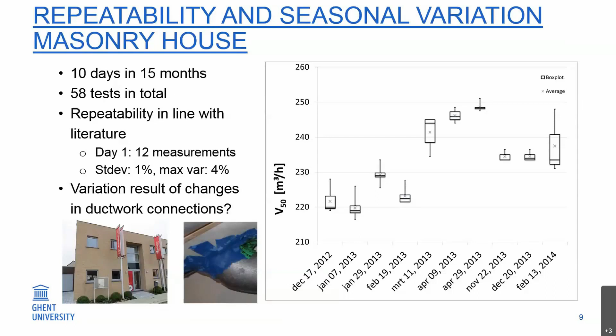You see the small picture on the left of the slide. The roof penetrations for the ventilation supply and exhausts are not sealed with the correct method. There is no rubber gasket used, but they used pieces of tape. And it's very easy to get an additional small leakage, or if you change it a little bit, you can tape it back. So this leads to differences in air leakage around the penetrations.